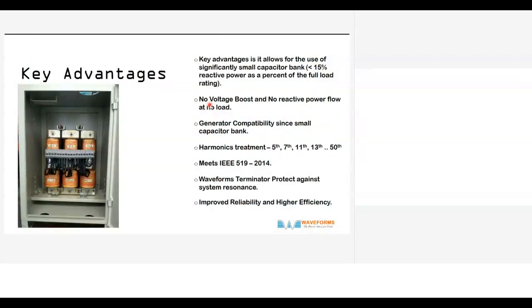So no voltage boost, no reactive power flow at no load. There's no voltage boost or no voltage drop also. Voltage also doesn't drop with it. So it is compatible with generator. Sometimes when there's overcapacitance, generator can be an issue. In this, you don't have a problem. So the harmonics treated are 5th, 7th, 11th, 13th, almost all the harmonics. So it filters all the harmonics, and it meets the IEEE 519 2014 standard.